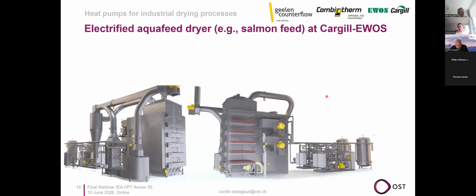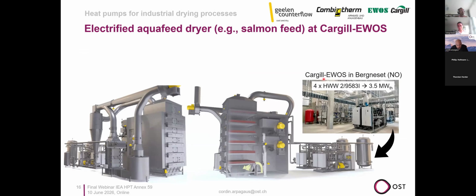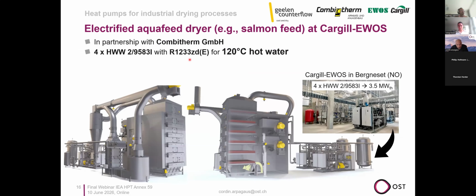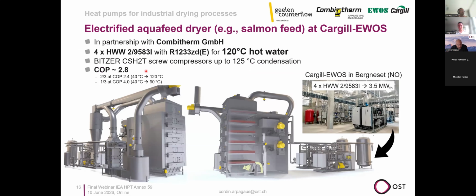Here we have more data, another picture of this dryer. We have here the 4 units which generate 3.5 megawatt of heating with Combitherm. They use HFO refrigerant and 120 degree hot water, some Bitzer compressors from Germany, screw compressors, and the COP is about 2.8. Looking at the whole drying process, 2/3 of the time the temperatures are from a 40 degree heat source, which is the exhaust humid air, I didn't tell that, to 120 degree, and another operating mode from 40 degree to 90 degree, which gives then an average COP of 2.8. The savings are 3,000 tons CO2 per year, and energy savings are also very, very substantial.